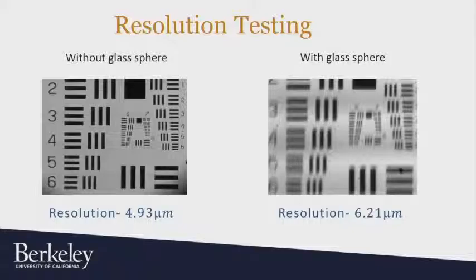The minimum resolution you can resolve is approximately 5 microns without the glass sphere. It only increases to approximately 6.21 microns with the introduction of the glass sphere. So even though the image does look fuzzy, you can still resolve very small optical factors.